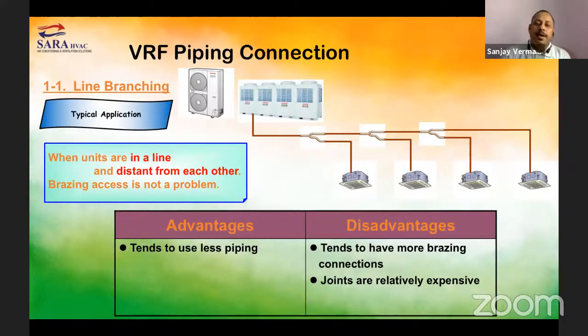But as we go further, the copper pipe size goes decreasing based on the indoor unit installations. Again, when units are in line and distant from each other, brazing access is not a problem. What happens? We do the brazing with these refnet joints with all the copper piping. And while doing the brazing, there will be nitrogen flow, so that the particles coming from brazing should not enter the copper pipe. It should get flushed continuously. So the advantage tends to use less piping, and the disadvantage tends to have more brazing joints. Joints are relatively expensive.